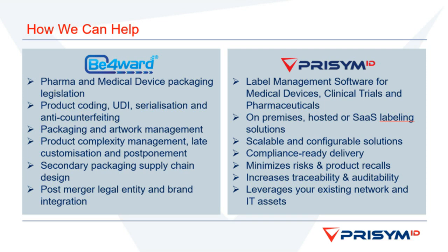Now, it's typical to include this data in the barcode, and this may be one or more barcodes on the label. Now, it's important to recognise that the DI component of that is actually key. What we're currently seeing is GS1, HIBCC and ICCBBA as the authorities which are licensing this.